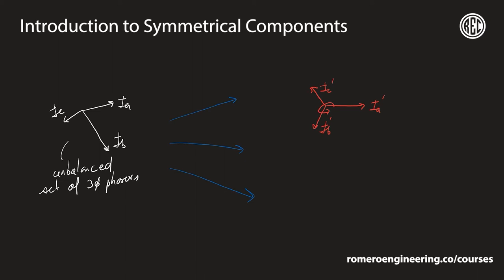The negative sequence set is also balanced — all three phasors have the same magnitude and are spaced 120 degrees apart. However, for an ABC rotation system, the negative sequence set rotates in the opposite direction. So what was the B phase location in the positive sequence becomes the C phase in the negative sequence, and vice versa — giving us IC negative sequence and IB negative sequence in those positions. The B and C phase locations are opposite between the positive and negative sequence sets.